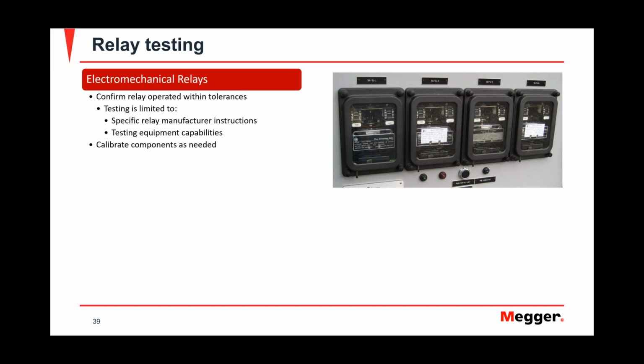Now going into the electromechanical relay testing. Confirm that the relay operated within the tolerance. Usually the testing is limited to specific relay manufacturer instructions. Know your testing equipment capabilities. There are certain test sets that have what they call a high burden mode, in which they're able to provide you more current at a lower voltage. But that higher current allows you to test these high burden coils, instantaneous coils used for electromechanical relays. So that's what I mean by know the testing capabilities of your equipment. Calibrate the components as needed, and if it's part of your job, that to me it's a separate science to know how to calibrate these things.